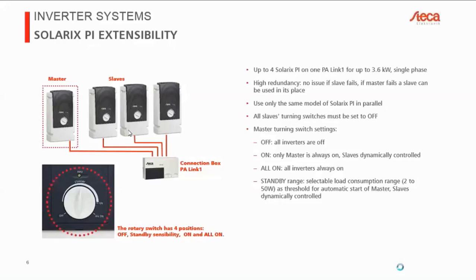The same thing would happen if you tried to connect an off-grid inverter, which is not designed for it, to a grid. In that case, the grid will always win. It will simply destroy your inverter and possibly cause serious damage. So that's the reason why we expect the slave switches all to be turned off. Because like this, if you lose communication, the device will simply stop running. If you have the switch turned to on or any other position apart from off, then if you take out the communication, the device will continue to run. And then, of course, you have a very real risk that there's a collision of the AC sine waves.